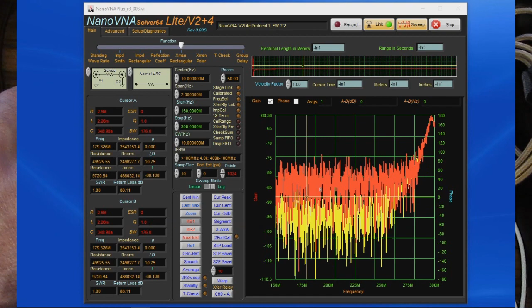So if we go back to the setup diagnostic page, you can see these 2 additional registers, E0 and E1. E0 is used for any frequencies below 100 megahertz, and E1 is currently anything above 100 megahertz. Let's just select the description and tip. And these are the equations for the different IF bandwidth. Here I'm calling it RBW. That's not really correct. I had asked DiSlord about changing that possibly, so he's agreed to that. Resolution bandwidth would be typically associated with a spectrum analyzer, not a network analyzer.